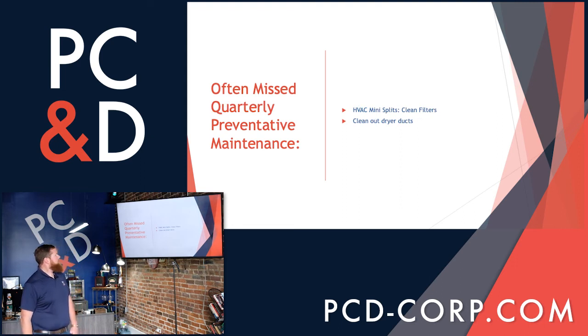All right, we'll continue on some of the most often missed. Again, we touched on the HVAC and the filters. So something else Dave and I noticed in the field pertaining back to HVAC are the mini split systems. Those are typically found in small offices or in dining rooms or even the kitchen area themselves. Typically these are mounted above head height and therefore are just a pain to clean. And we've noticed over the years that they have been neglected and therefore caused failure. So that's something to keep in mind as you're going through.